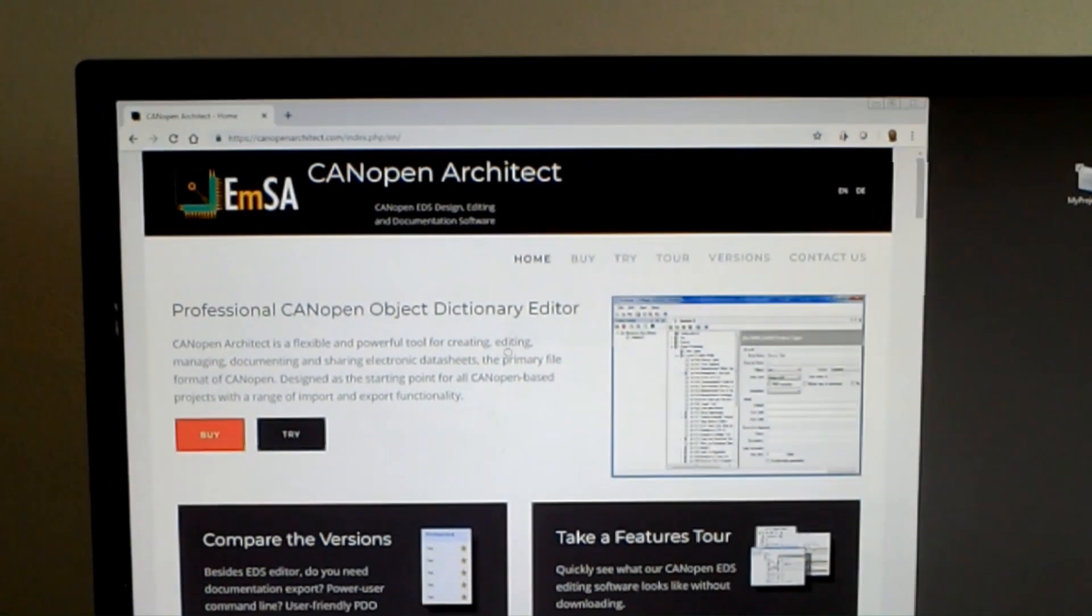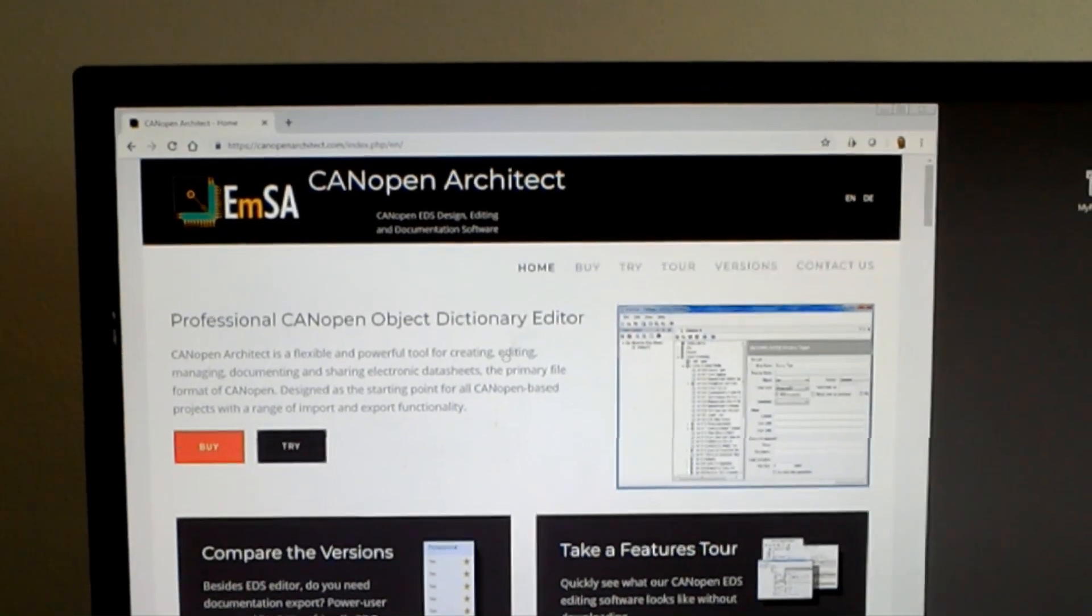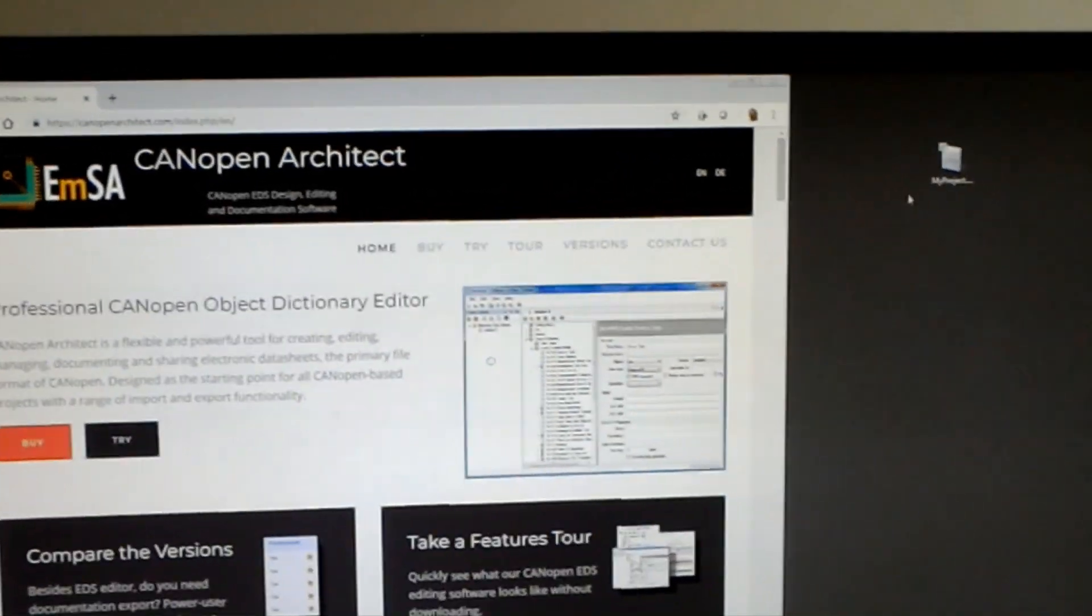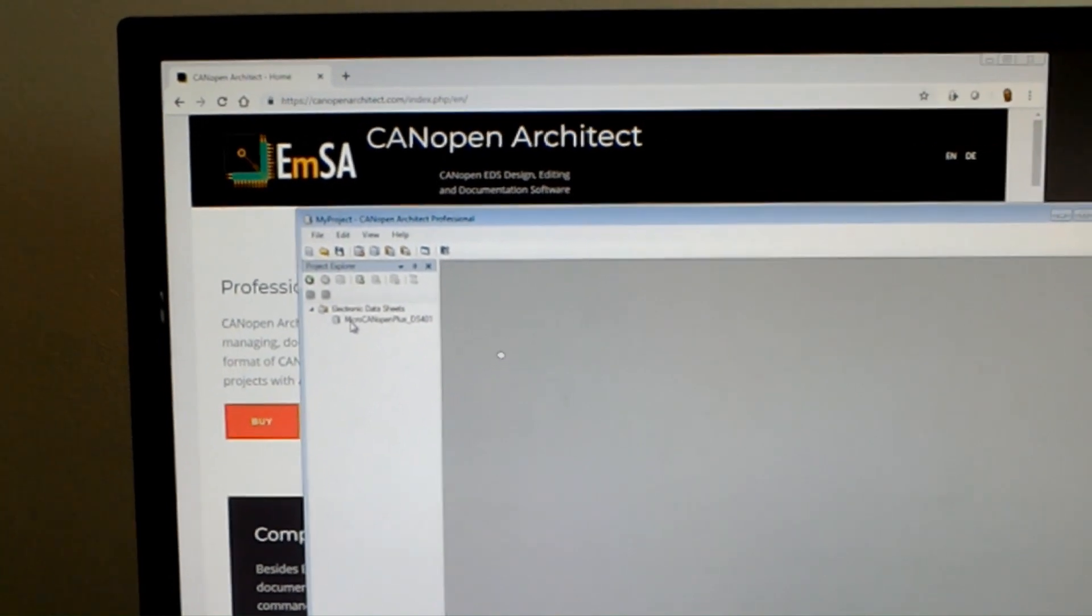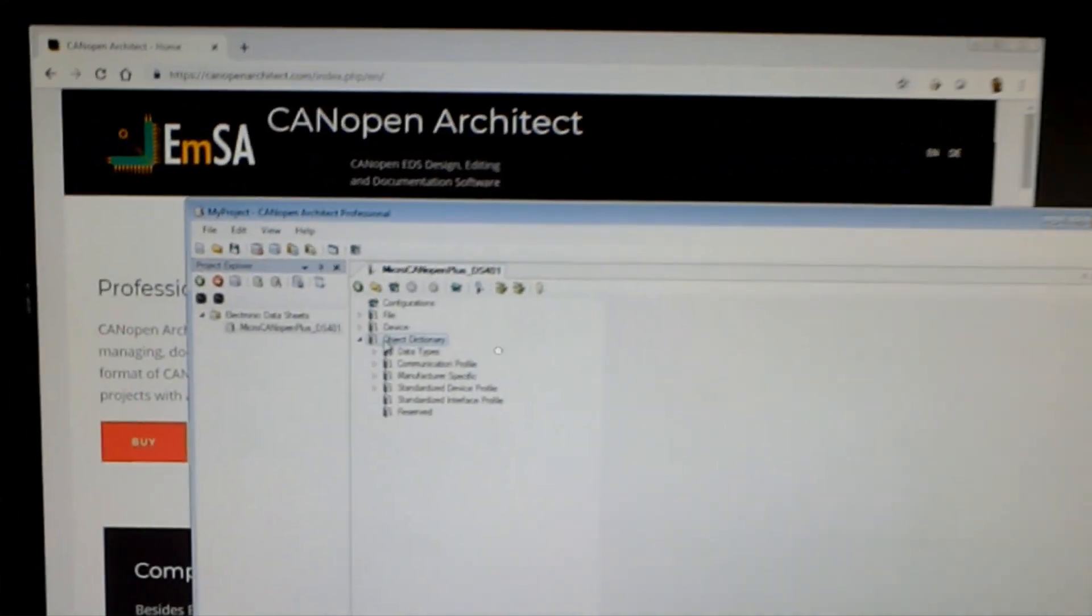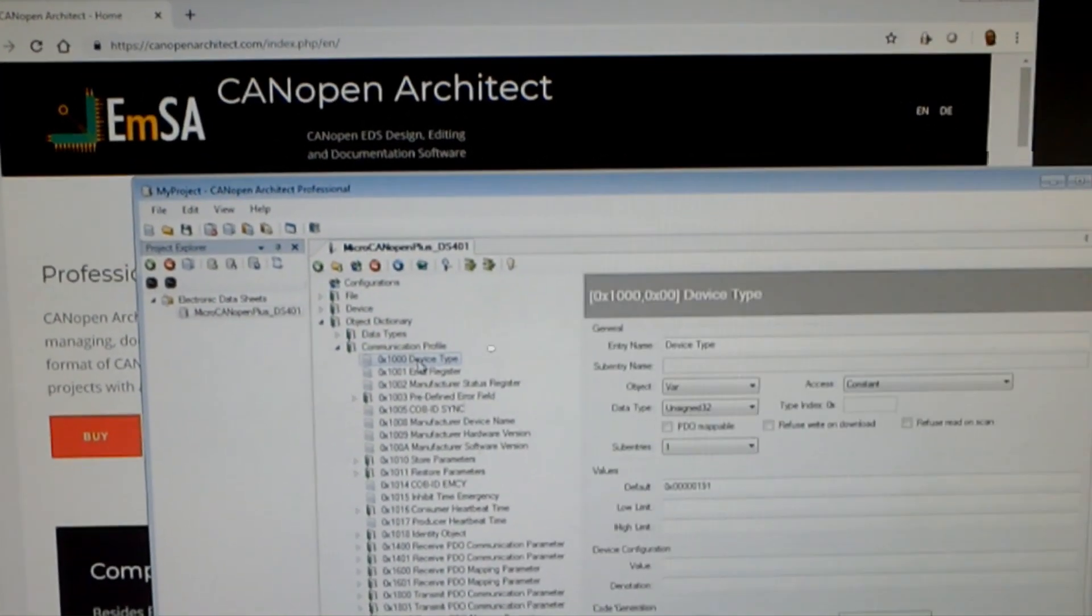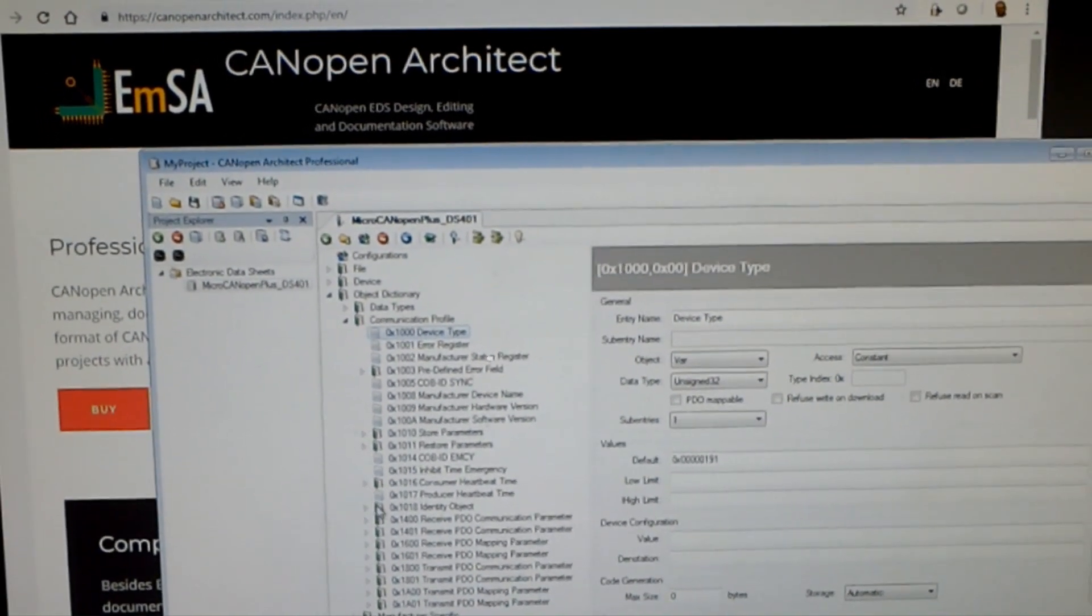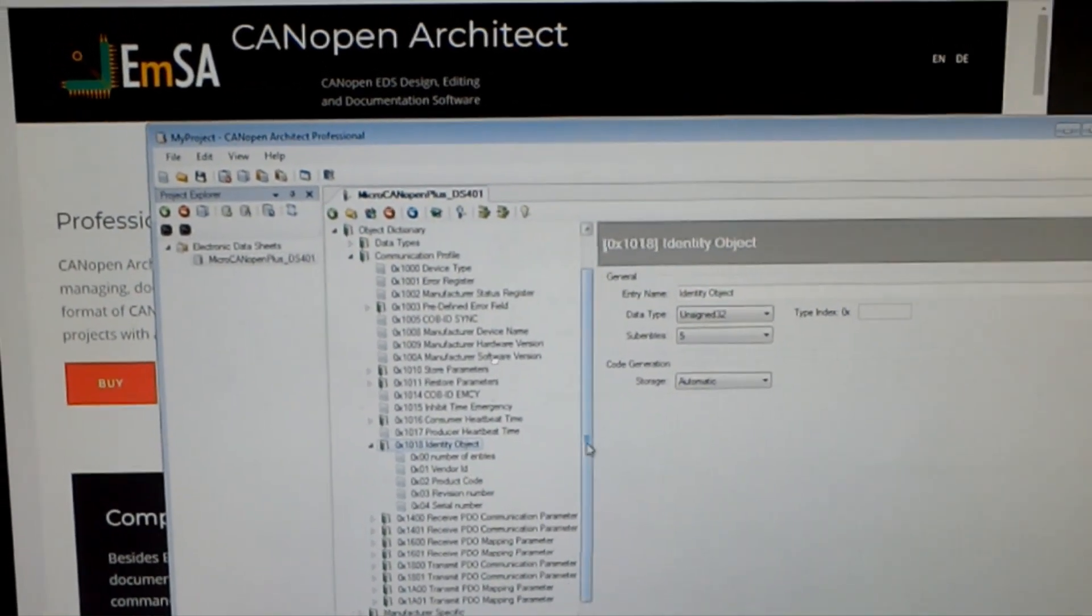We will now use the CANopen Architect and editor for the EDS, the electronic data sheets. The electronic data sheets are an electronically readable version of the object dictionary and its configuration. This is an example of a regular I/O node with digital and analog input. We can see that the object dictionary is divided into several areas. We have the communication profile with our 1000 device type, the data type and the access type. We also have here at the 1018 the identity object with the sub-entries as discussed.